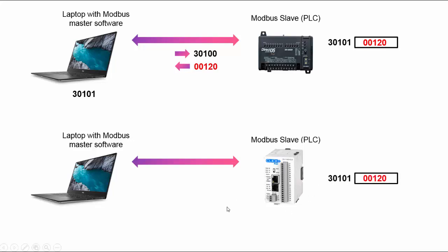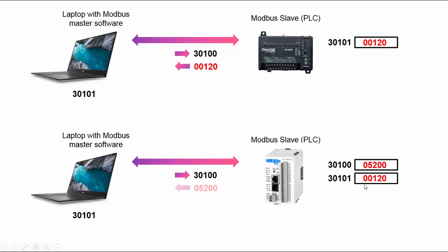So we have this again, we type in this and it sends out 30,100. However, since this doesn't implement it, it actually goes literally to 30,100 because it doesn't implement plus one offset and sends back 5,200 which is the value at 30,100. It sends back the wrong value.